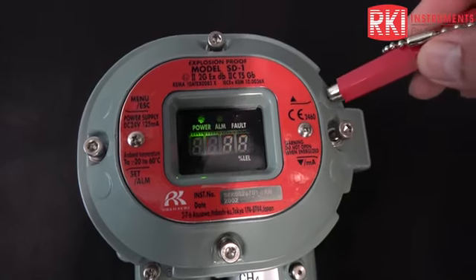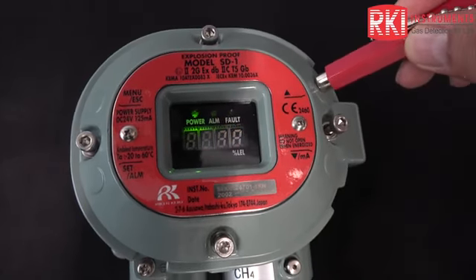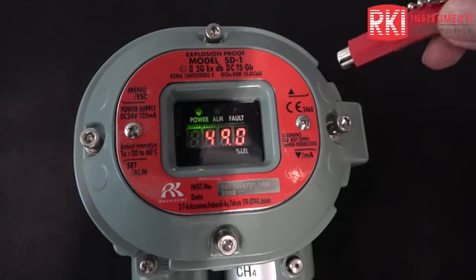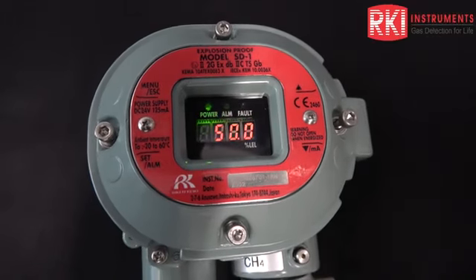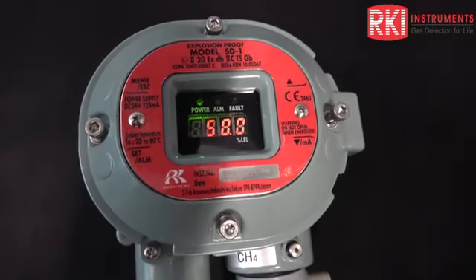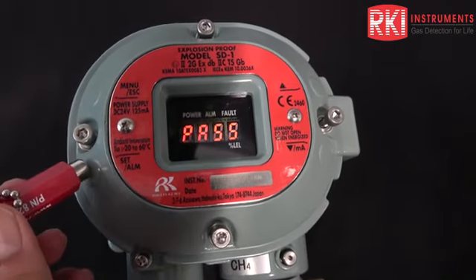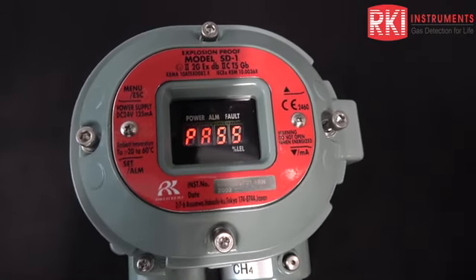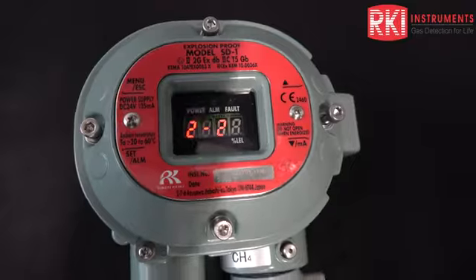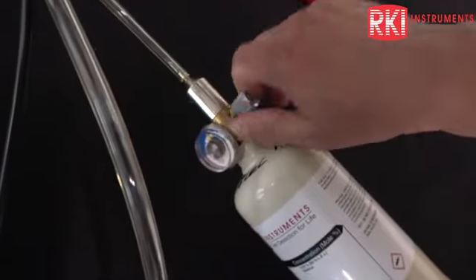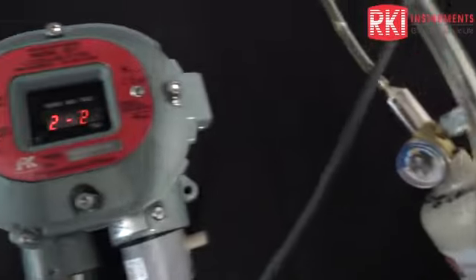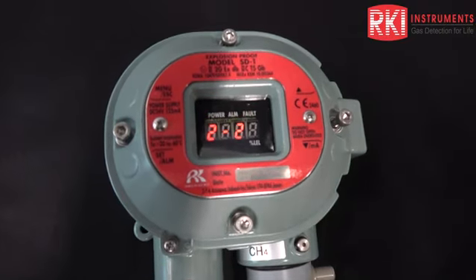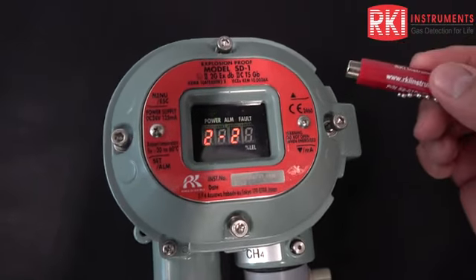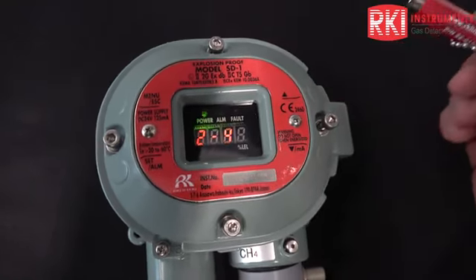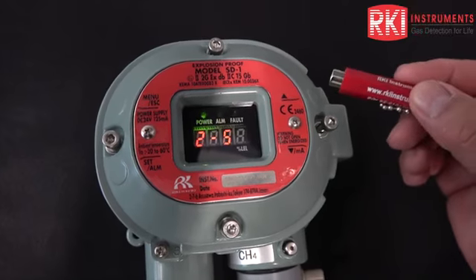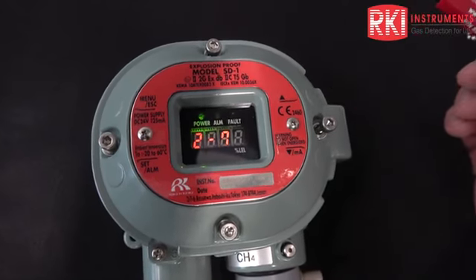Okay, a little bit too far there. All right, there's 50. And then once I'm at 50, go back to the set pad and pass. So I'll turn my gas off. I close up the regulator valve. I'm back to 2-2. Now I want to advance to 2-7, which is the point where I can go back to the main menu easily.